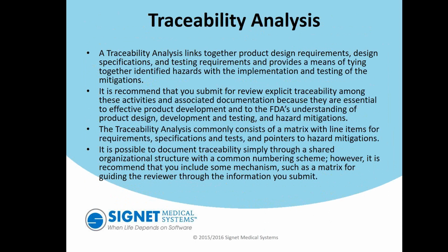So this traceability will show to the FDA that not only have you said you're going to develop this particular type of communication between a wireless controller and your piece of hardware, but you've actually implemented it in this fashion using these types of designs, and you've tested it in this way using this test. It is recommended that you submit for review explicit traceability amongst these activities, not just kind of an idea that we use the software requirements to develop this, some statement. That really doesn't work.